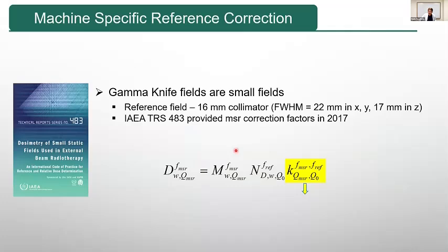So to solve that problem, in 2017, the IAEA published Technical Report Series 483 for small field dosimetry. In this report, they define a reference field for each device. For GammaKnife, they say the 16 millimeter collimator field is a reference field. And they also introduced a correction factor. I call it the MSR correction factor.